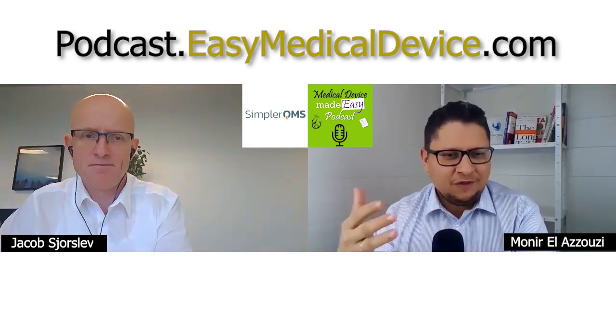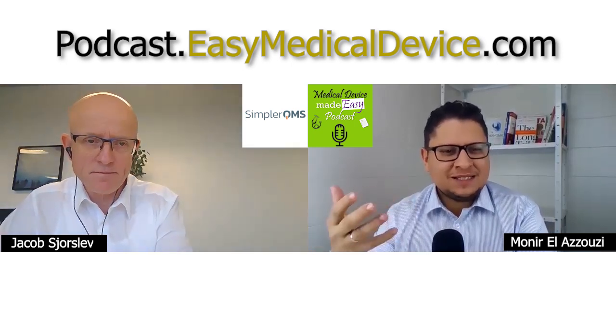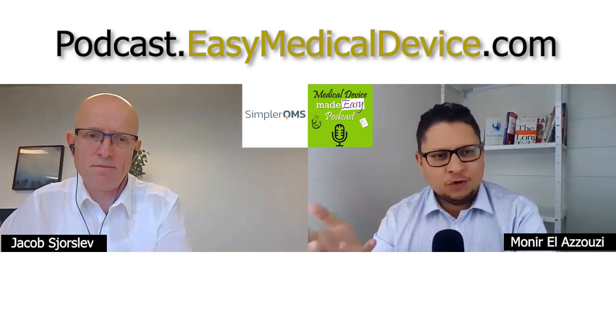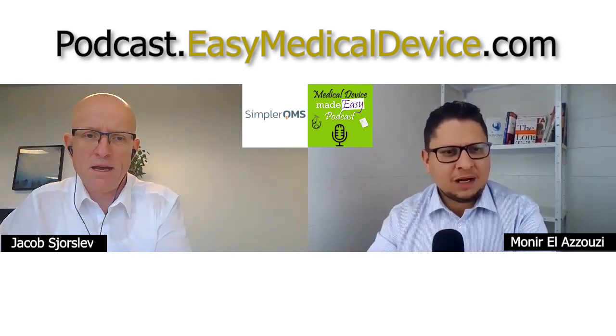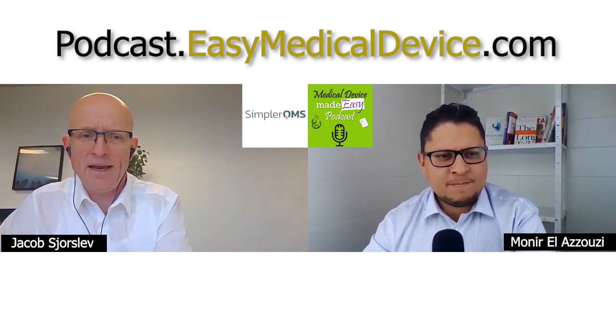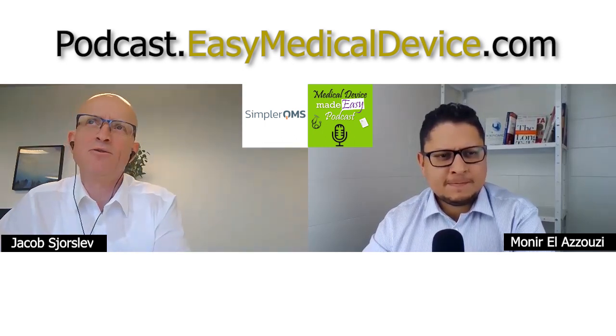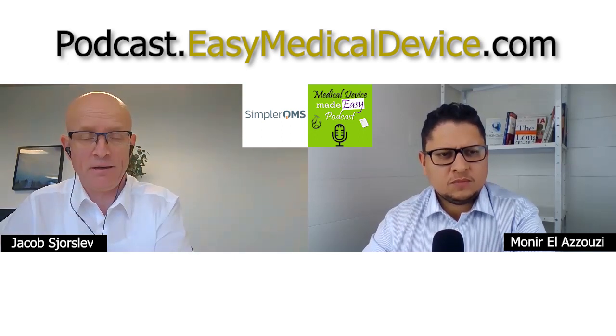Because when you said the first thing, does it need to be validated, it means that we can say yes or we can say no. So it's not mandatory to say yes, we have to be validated. And when you go through this exercise, you also become very specific about what the intended use is. And the intended use also goes into the risk analysis that you have to do in order to say, okay, what can go wrong if the process that I have inside of the system will actually fail.